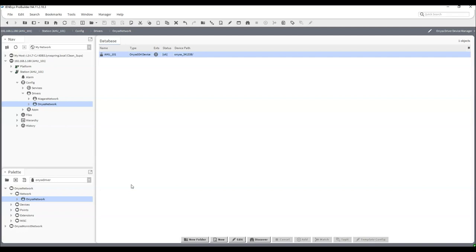Each XMIO board probably will have a different piece of equipment, so I could be running an air handler on this one, maybe another air handler on the next one, and maybe even a small hot water or chilled water plant on the following one. So that way, when a technician or another programmer comes behind the job, they can actually see what device they're working on.